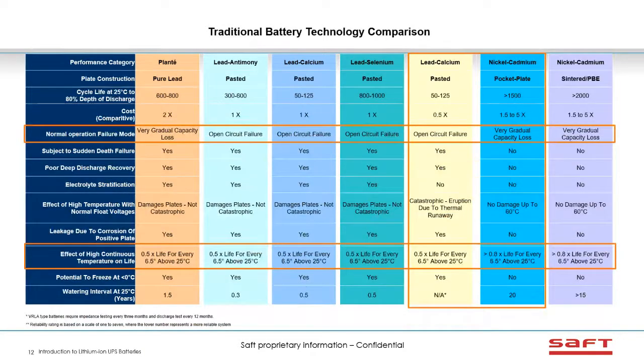A little bit more comparison here, to highlight the failure modes and the effect of temperature of those two technologies, whereas the lead acid batteries can fail open circuit, and the NiCads just have a very gradual capacity loss over its life.